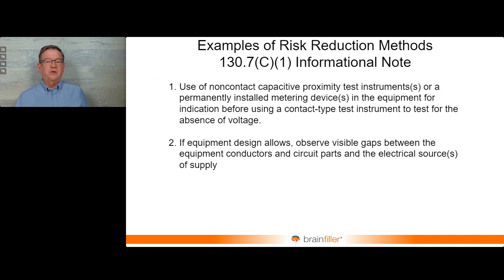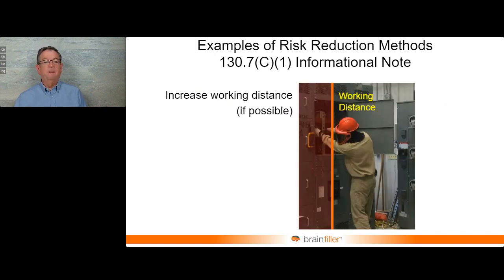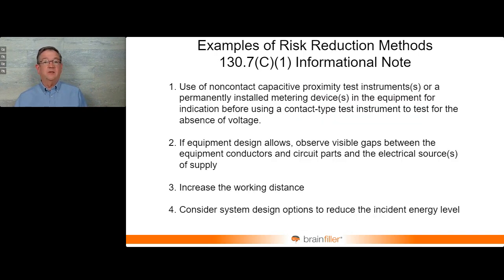If you can look at the equipment, see visible gaps or things are racked out, that's a good verification. Increase the working distance, back up, the energy drops substantially if you can increase the working distance. And consider alternate design methods to try to reduce the incident energy level.